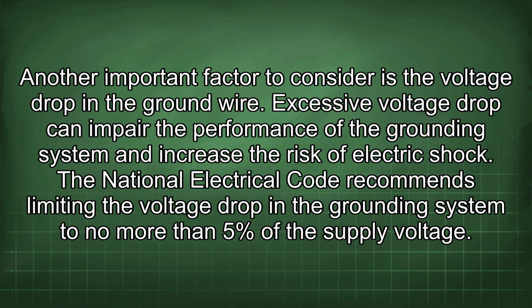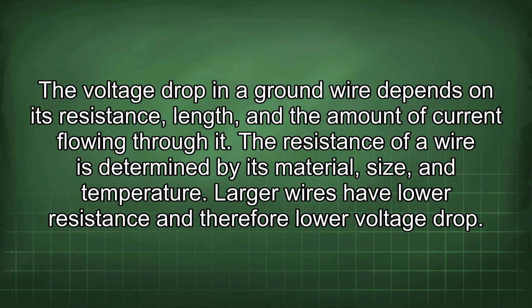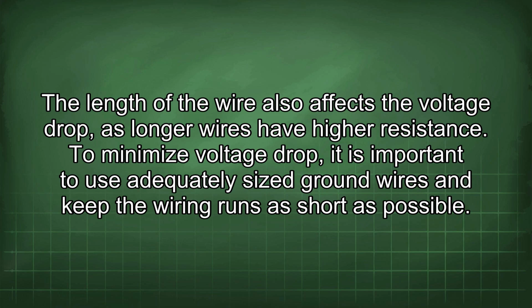Another important factor to consider is the voltage drop in the ground wire. Excessive voltage drop can impair the performance of the grounding system and increase the risk of electric shock. The National Electrical Code recommends limiting the voltage drop in the grounding system to no more than 5% of the supply voltage. The voltage drop in a ground wire depends on its resistance, length, and the amount of current flowing through it. The resistance of a wire is determined by its material, size, and temperature. Larger wires have lower resistance and therefore lower voltage drop. The length of the wire also affects the voltage drop, as longer wires have higher resistance. To minimize voltage drop, it is important to use adequately sized ground wires and keep the wiring runs as short as possible.